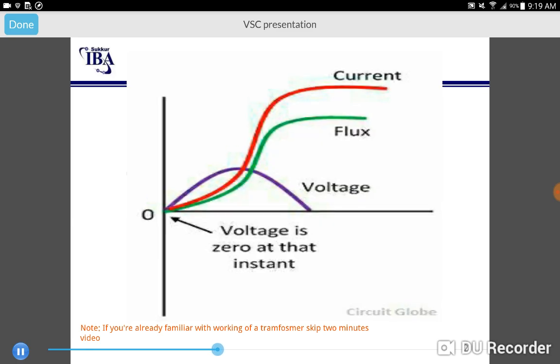During the energization of a transformer, the voltage is at its 0 point, and the flux has also started at 0. So, for a rising voltage just started from 0, the magnetic flux will reach approximately twice its normal peak as it integrates the area under the voltage waveform's first half cycle. This amount of flux, because of the non-linear characteristics of the magnetization curve, causes saturation of the transformer. As seen from the figure, exceeding flux from the knee point results in large magnetizing current that in some circumstances can be 10 times the rated current in a transformer. We will not go through the mathematics behind this process.